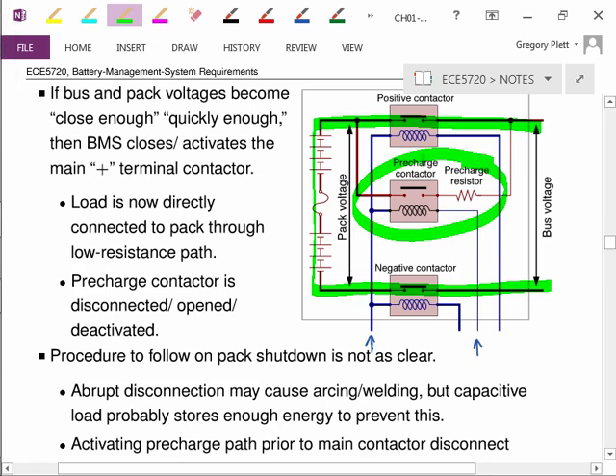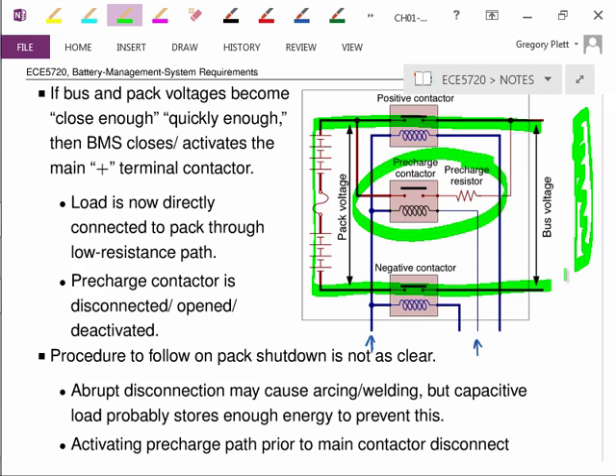We do have to watch a few things, though. For example, there's the possibility that the load is somehow faulted. I need to make sure the precharge resistor does not get too hot, because I'm continually drawing a lot of current through it. If it gets too hot, I just open the precharge contactor and declare some kind of operational fault. If it takes too long to charge the capacitive bank of the load, that probably also means there's a load fault, and we probably want to open the contactor and declare that we think there's a problem.